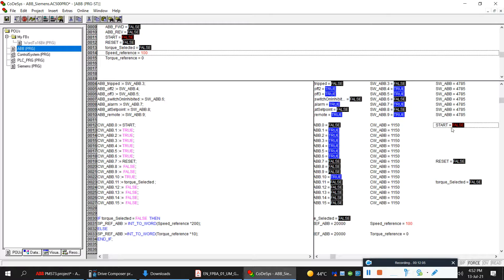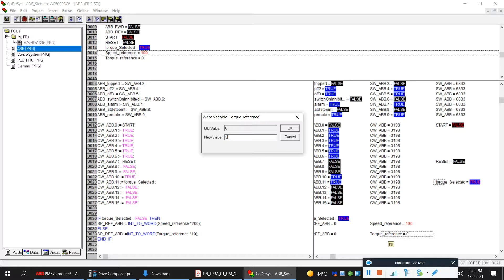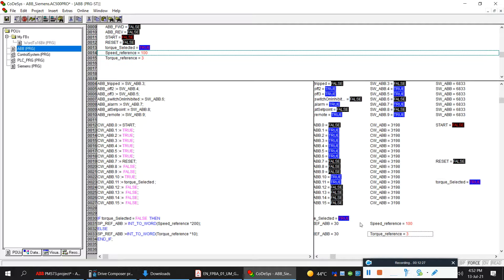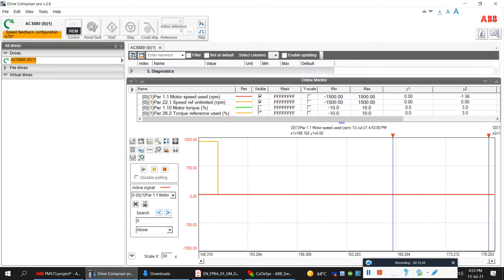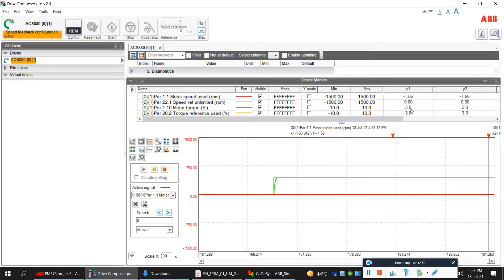When I started the motor at full RPM it was around four percent torque. Now let's select torque control and give a torque reference of three percent. Now I'll give a start command. You can see the motor is not moving, but torque is being generated in the motor. Exactly as I set — three percent reference — and the motor torque is kept at three percent. Now let's stop and give a higher torque reference to actually run the motor.